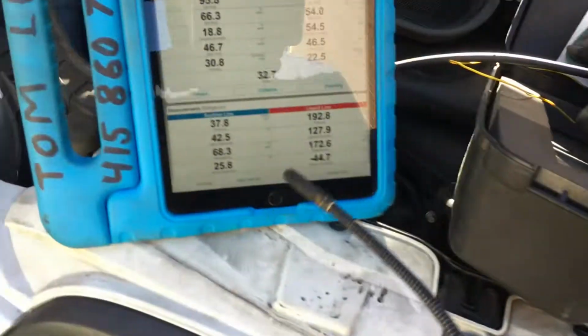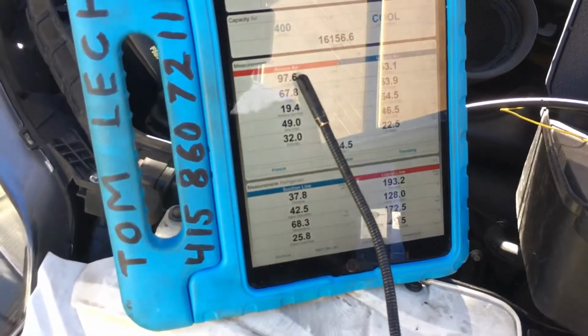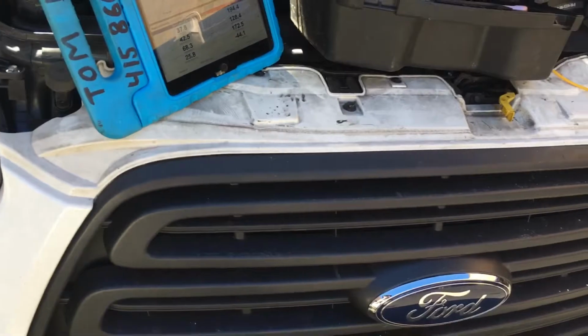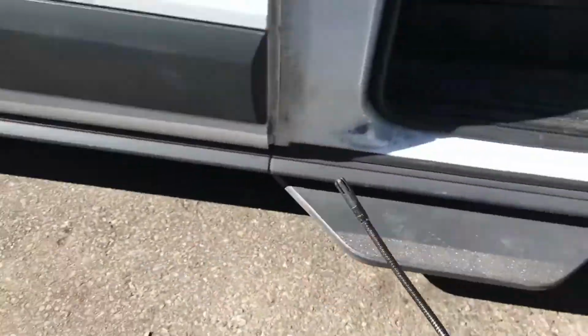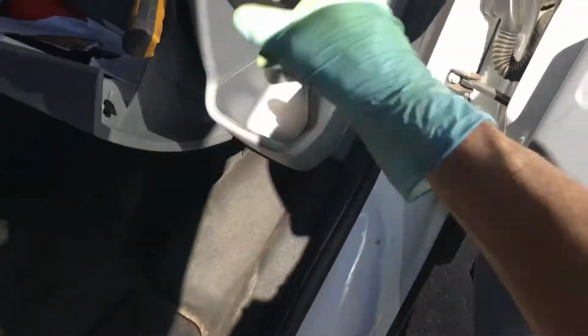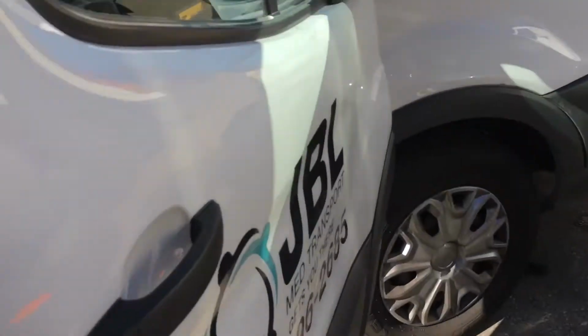No, wrong one. That's the discharge. It's in my hand. 97 degrees, and it's not 97 degrees. Let's take this way over here. Let's let it cool down because it's really hot. Let's stick it up under where it's pulling its air from. It's actually pulling the air at the inlet, right about inside here, for the recycle. Let's see what that temperature is.